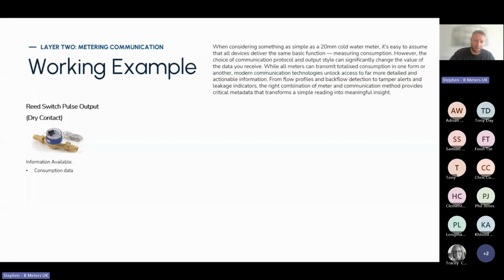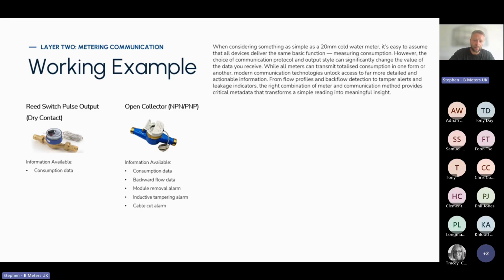However, as we've discussed, reed switch pulse outputs aren't necessarily the most reliable, so if data is important, it's not something I would particularly promote. The open collector, for example, is the same type of pulse output, giving consumption data, but you can also configure the unit to give you backward flow data, along with certain alarms - module removal alarm, inductive tampering alarm, cable cut alarm, magnetic tampering alarm.